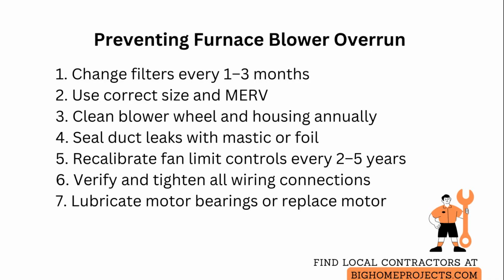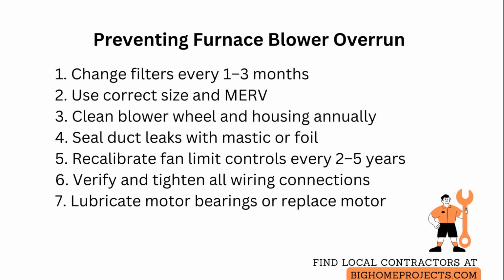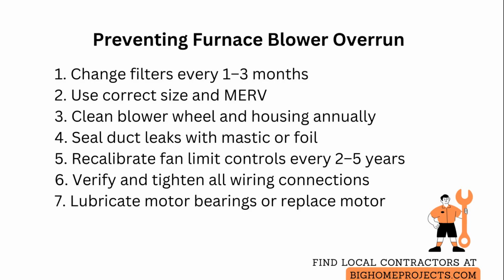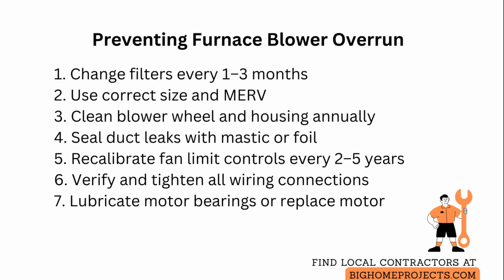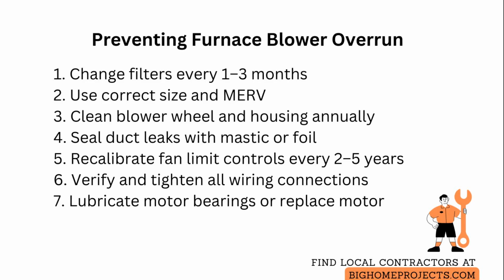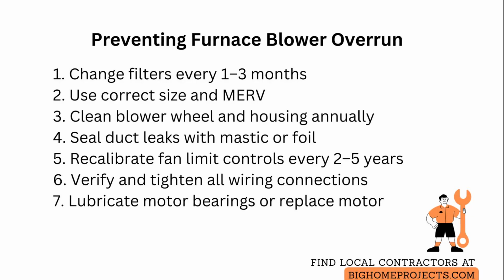Verify all wiring at the blower motor, control board, and thermostat for loose terminals, frayed insulation, or corrosion, and tighten or replace connectors while ensuring power is off to avoid shocks. Lubricate motor bearings if the motor has oil ports, and replace motors that show axial play or excessive noise, since worn bearings accelerate overrun conditions.